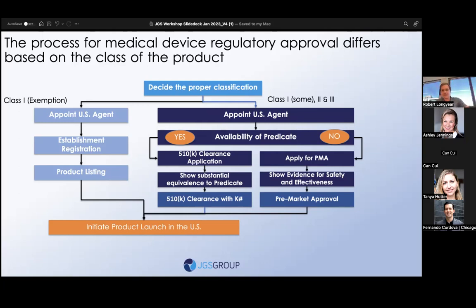So you're going to go through there and say, hey, our device really does what this does, and it has the same intended use. So you'll fall under that category. We'll go through and request the filings from companies that have gone before you and established that category and classification, and review what they did to try and match that as close as possible, typically.